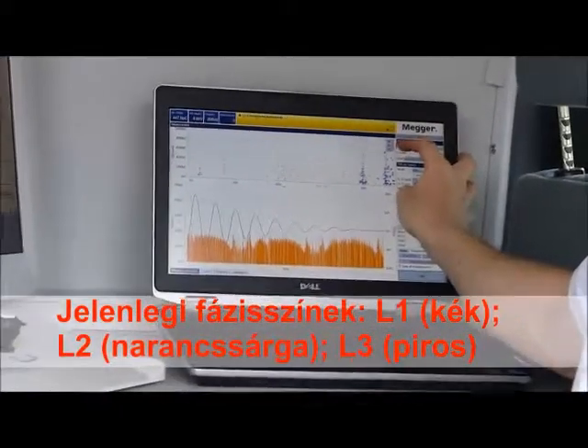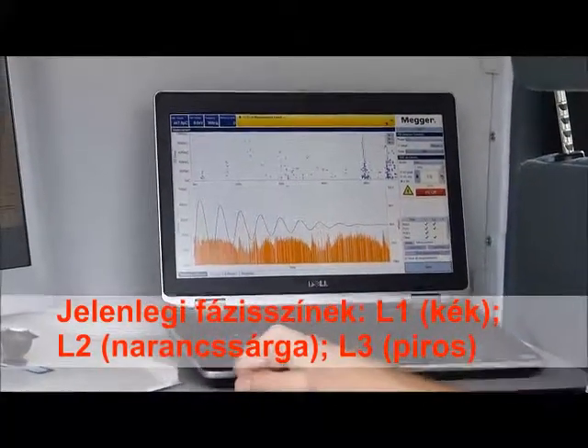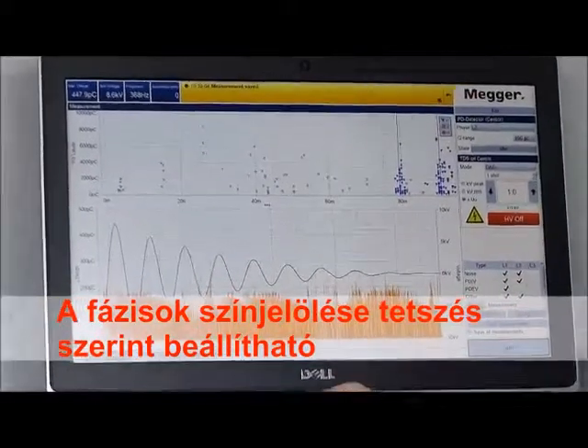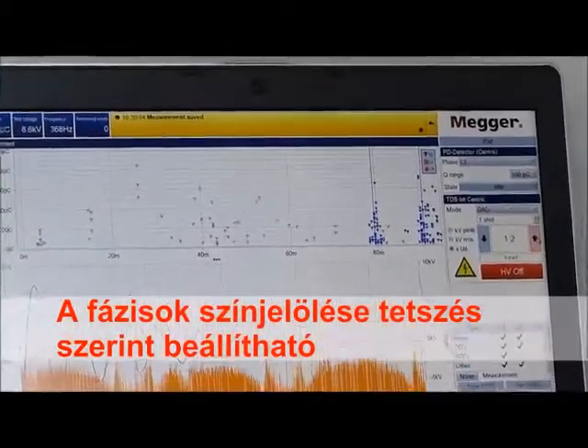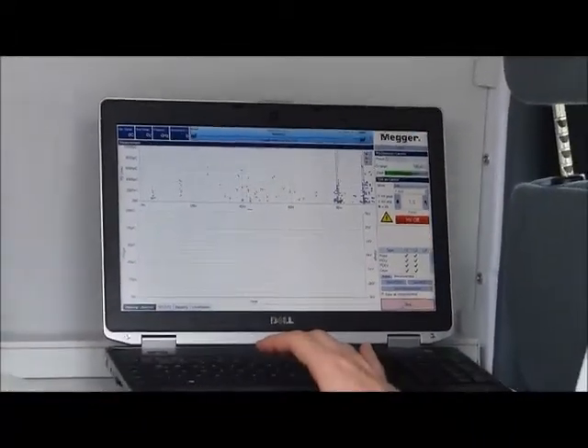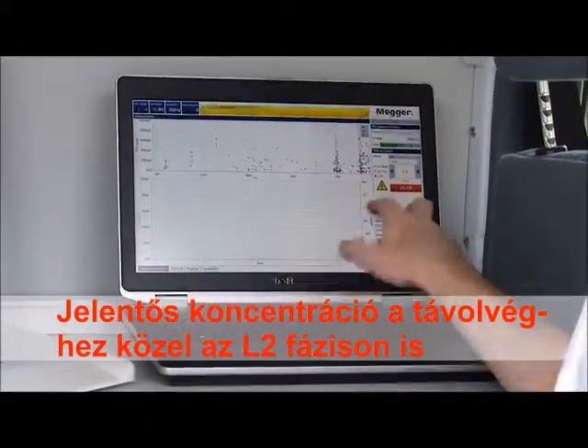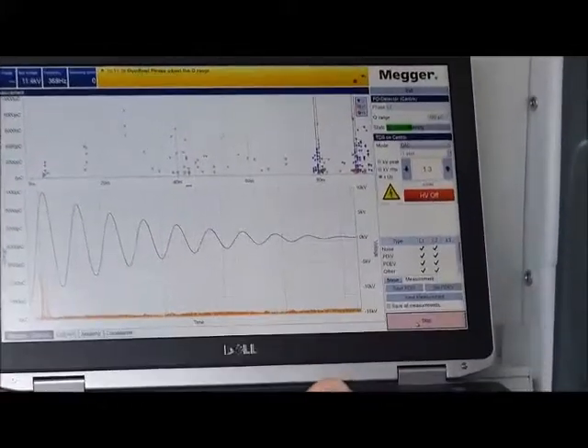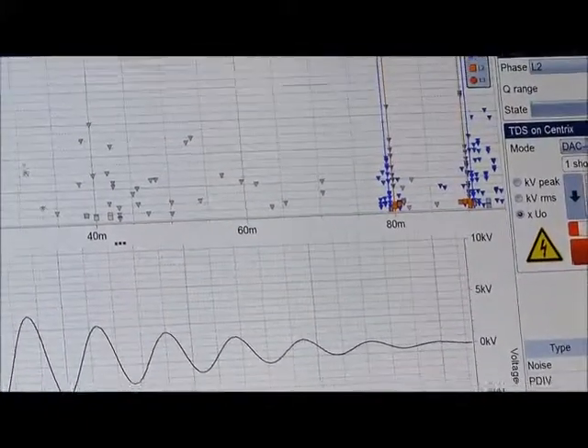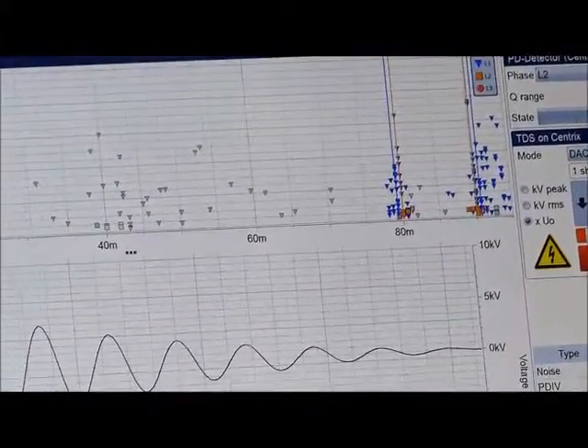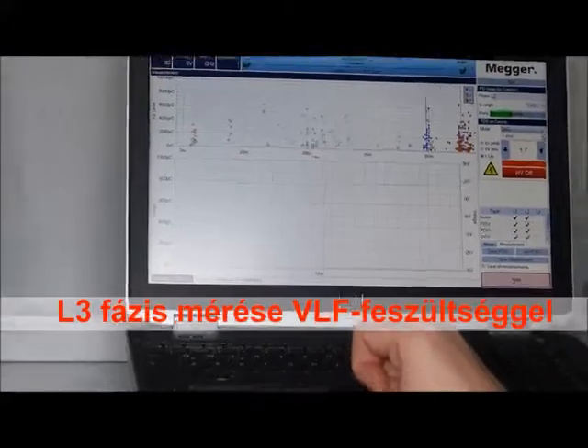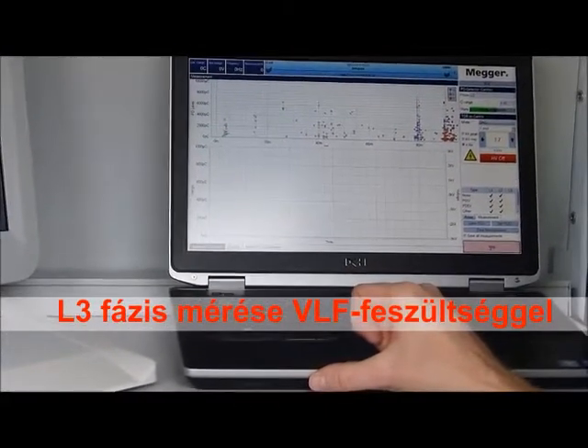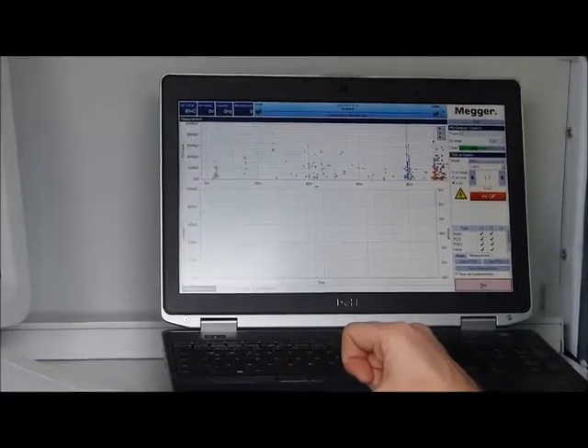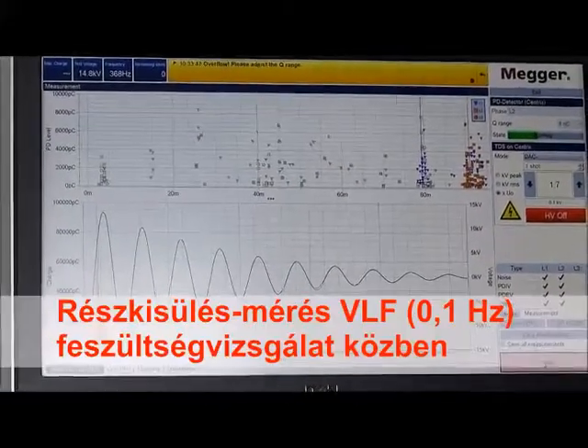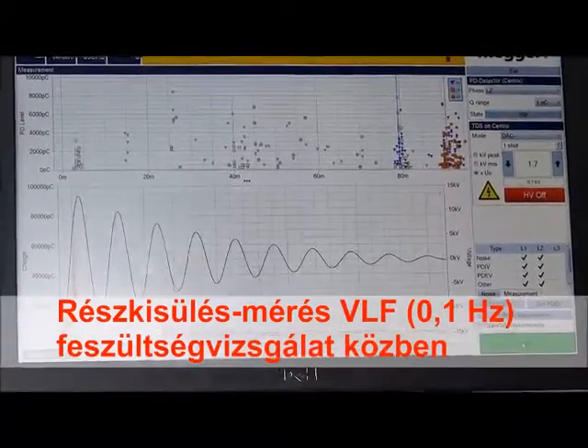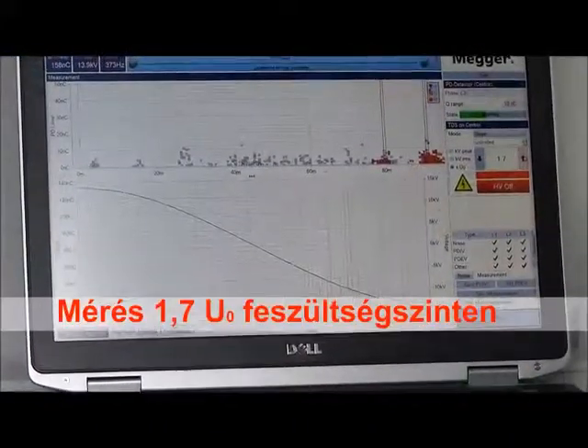Blue for L1, yellow for L2, and red for L3. But it seems to be the same location for that weak spot as for the L1 phase. I would say for the L3 phase we can also do it with the VLF, with the cosine rectangular. So you can see, okay, during the test you could also make the partial discharge measurement, producing the waves continuously.